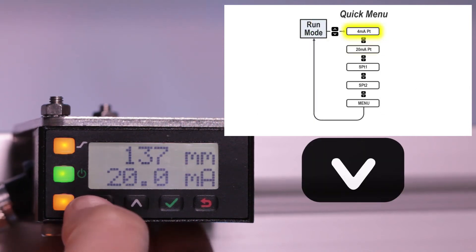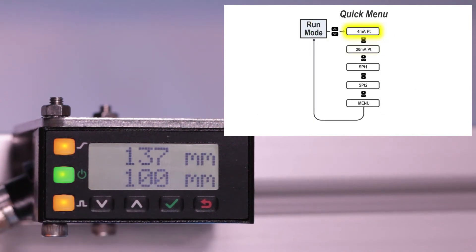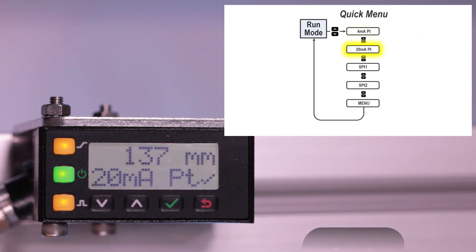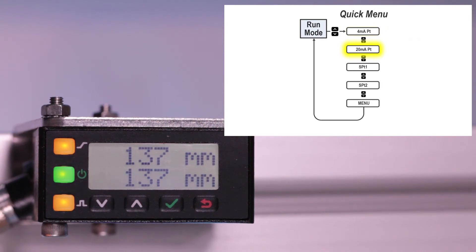Click down. The top line continues to display the current distance measurement. The bottom line of the display now shows us the current setting for the 4mA point or the 20mA point. This verifies the 20mA point was taught at 137mm.